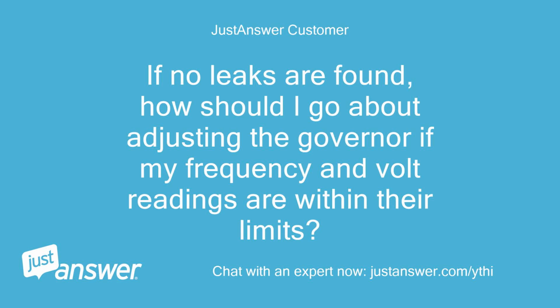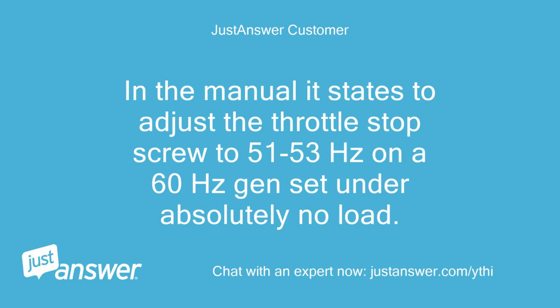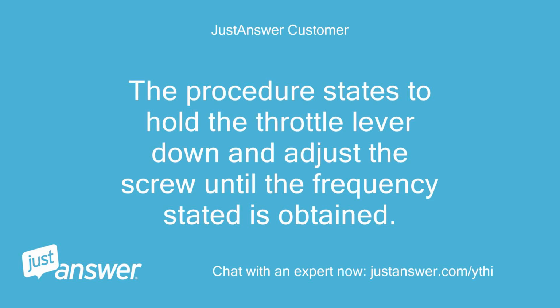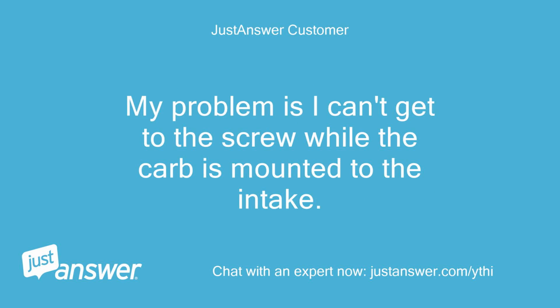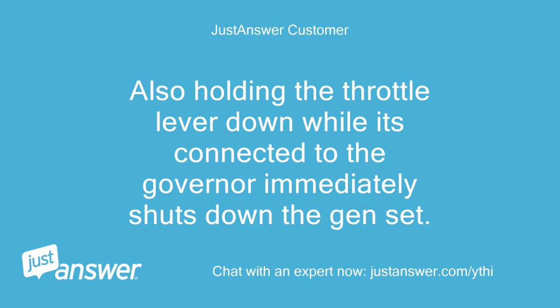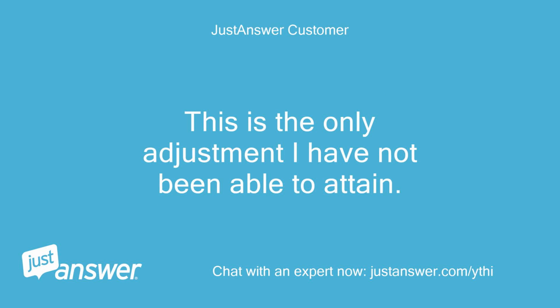If no leaks are found, how should I go about adjusting the governor if my frequency and volt readings are within their limits? In the manual it states to adjust the throttle stop screw to 51 to 53 Hz on a 60 Hz gen set under absolutely no load. The procedure states to hold the throttle lever down and adjust the screw until the frequency stated is obtained. My problem is I can't get to the screw while the carb is mounted to the intake. Also, holding the throttle lever down while it's connected to the governor immediately shuts down the genset. This is the only adjustment I have not been able to attain.